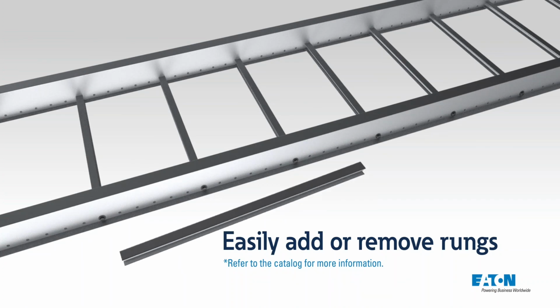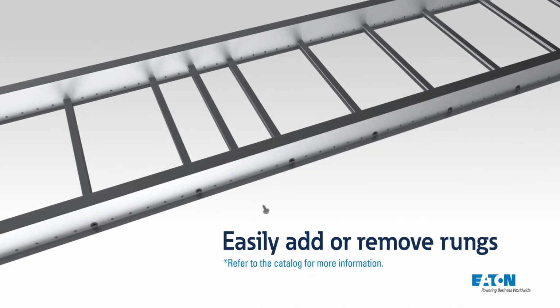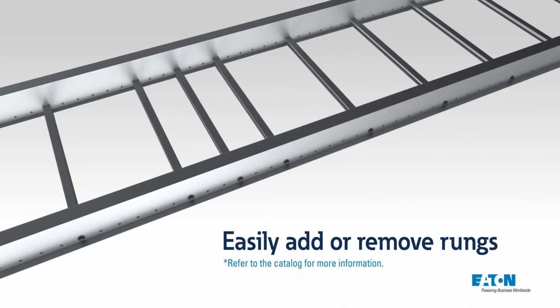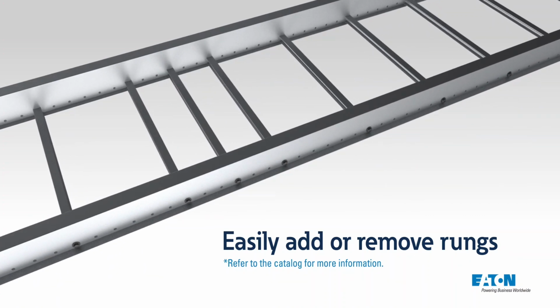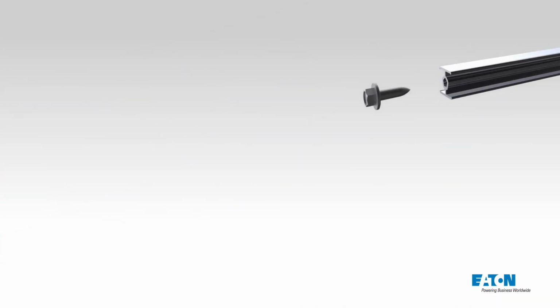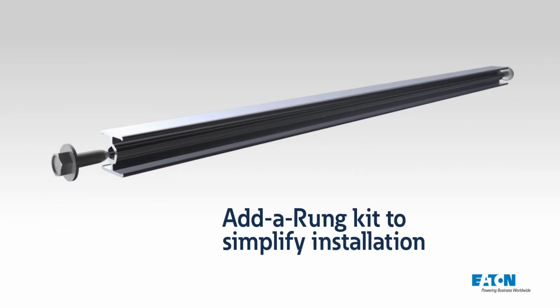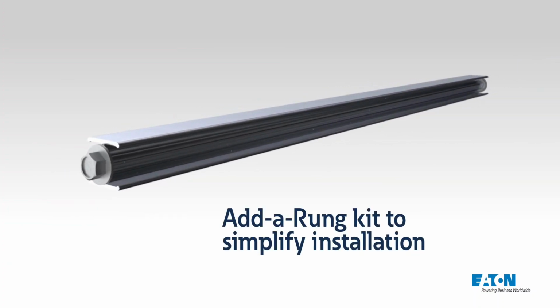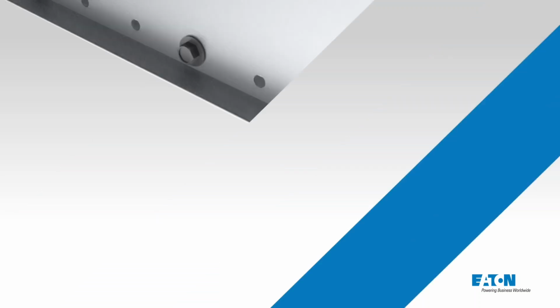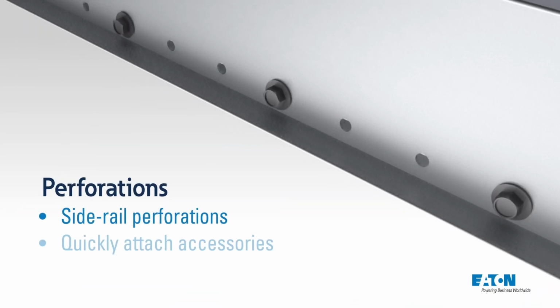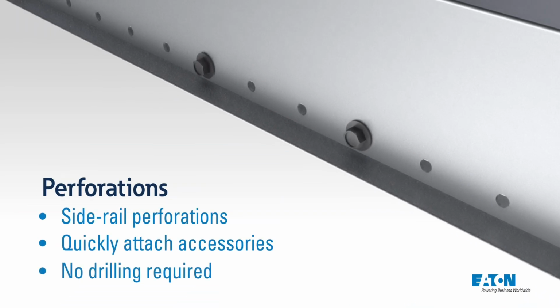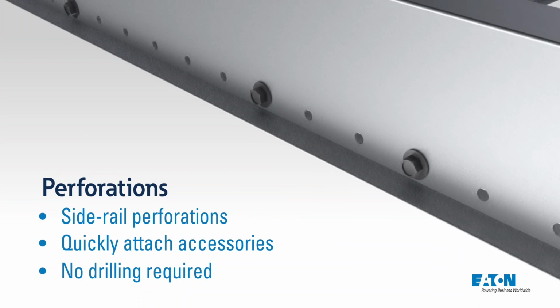Installers no longer need to cut rungs in the field. Simply add a rung onto the bolted tray for additional cable support or to drop cables at a precise location. To speed up the process, we offer an Add a Rung kit that has everything you need to add a rung quickly and easily. The Quick Rail system has perforations along the side rail, which allows the attachment of accessories without having to drill holes.